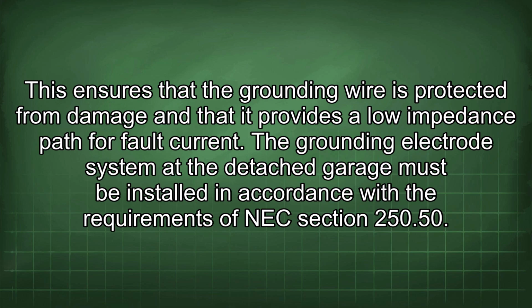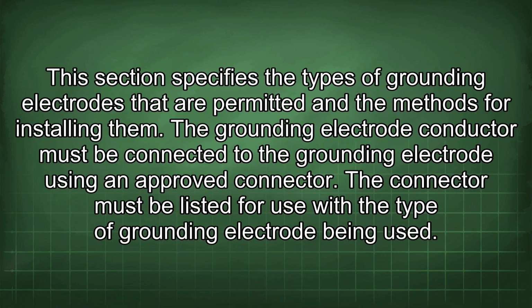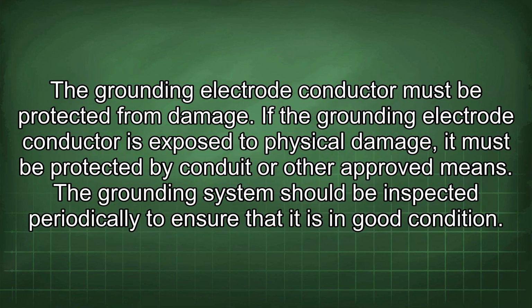The grounding electrode system at the detached garage must be installed in accordance with the requirements of NEC Section 250.50. This section specifies the types of grounding electrodes that are permitted and the methods for installing them. The grounding electrode conductor must be connected to the grounding electrode using an approved connector. The connector must be listed for use with the type of grounding electrode being used. The grounding electrode conductor must be protected from damage. If the grounding electrode conductor is exposed to physical damage, it must be protected by conduit or other approved means.